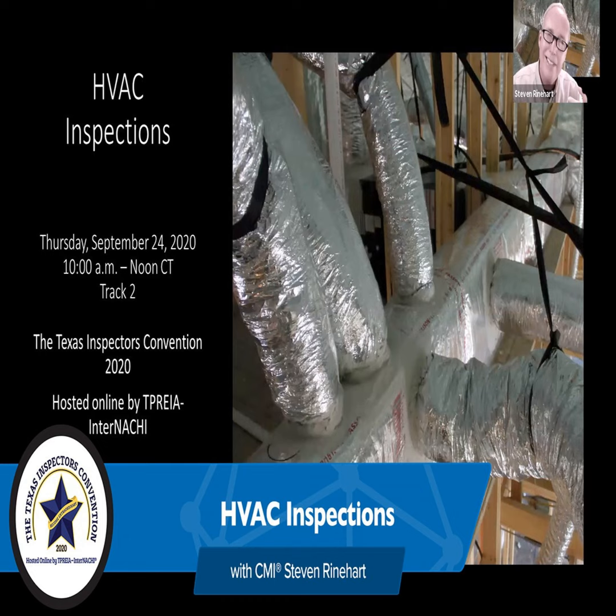Missing duct insulation: vermin are the biggest critters up there. They will chew through it looking for moisture, water, being warm in the winter. That's the most common cause there. Absence of airflow: do go to every room. I'm not talking about putting a flow hood on the register. It's as simple as holding your hand up in front of it. Do you feel air coming out? That's what you're looking for there.